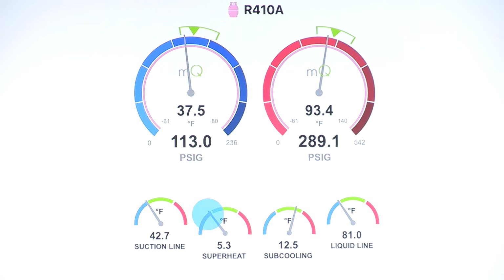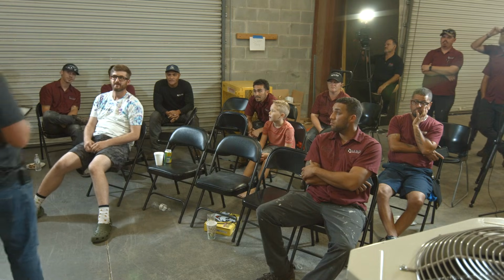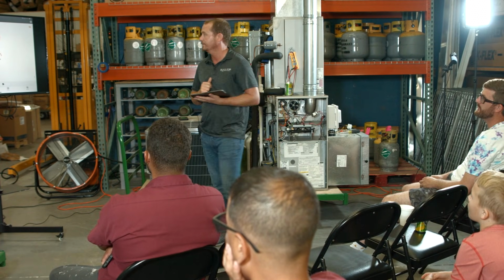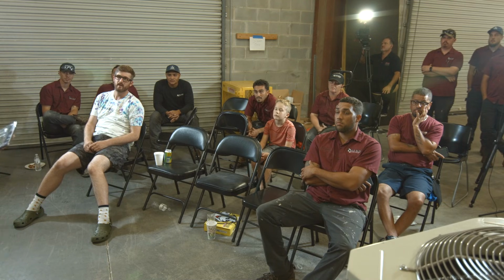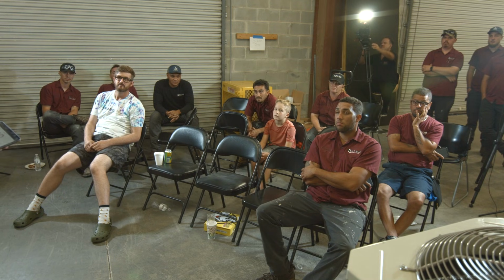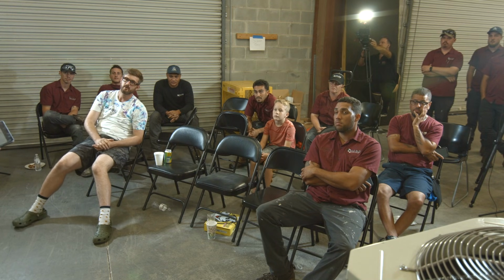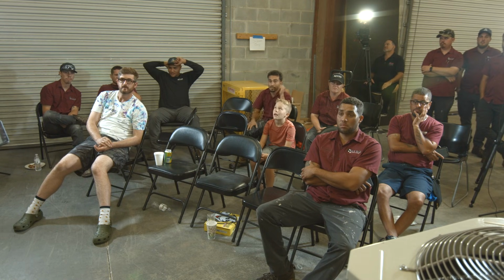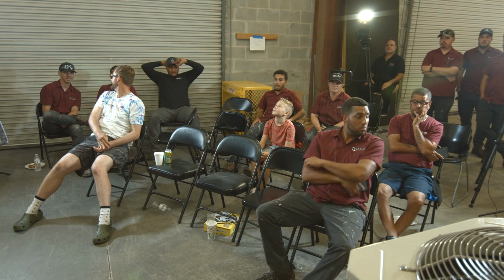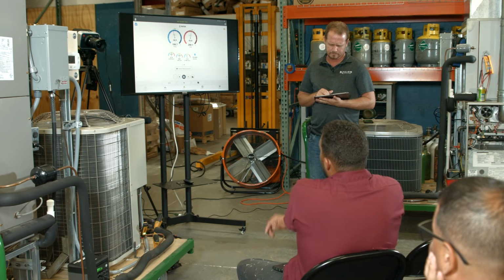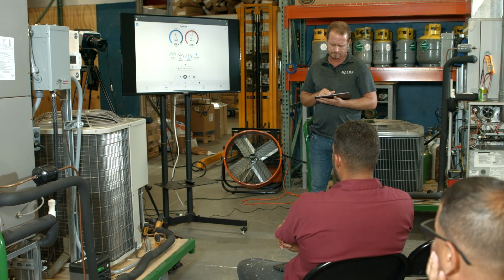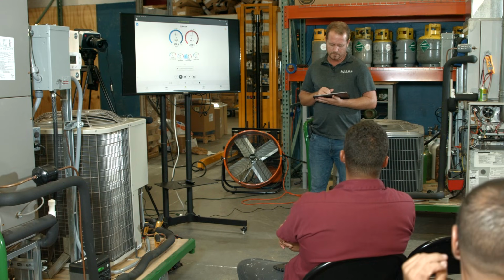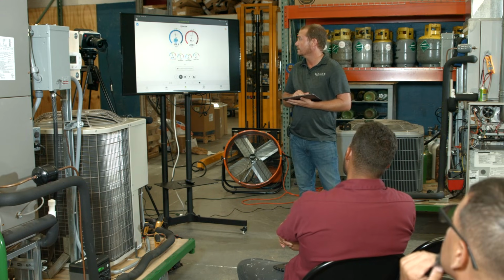Interestingly enough, it's still not going to freeze. Yeah, I know, because we have enough load in here. The temperature dropped significantly. Well, we have a 76-degree return even with all that resistance. Actually, it's starting to drop more now. Yeah, it'll get there. You trying to ice it up? Oh yeah, let's ice it up. Make ice. Yeah, we're definitely diving now.